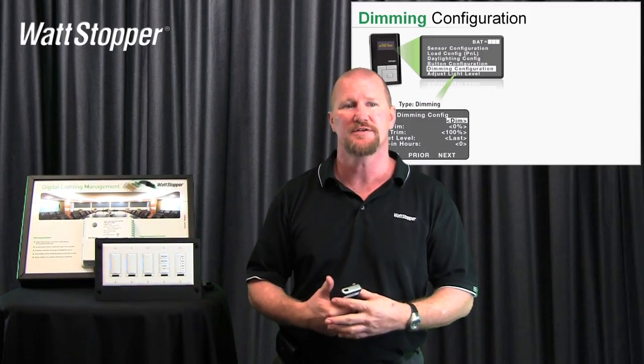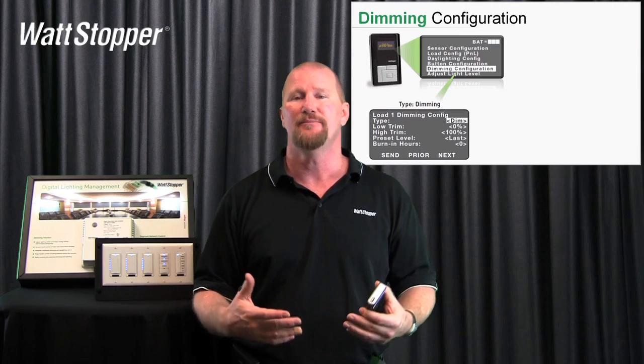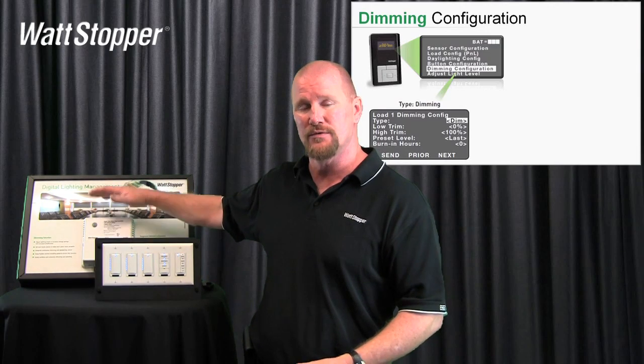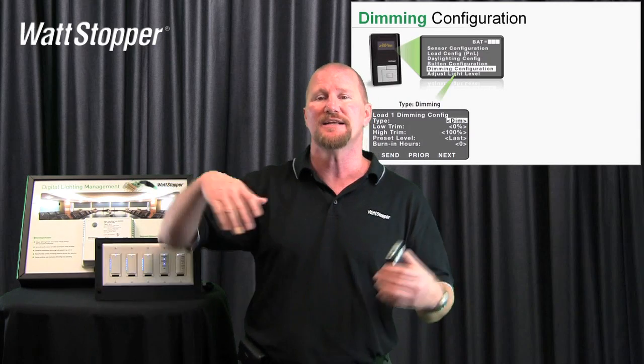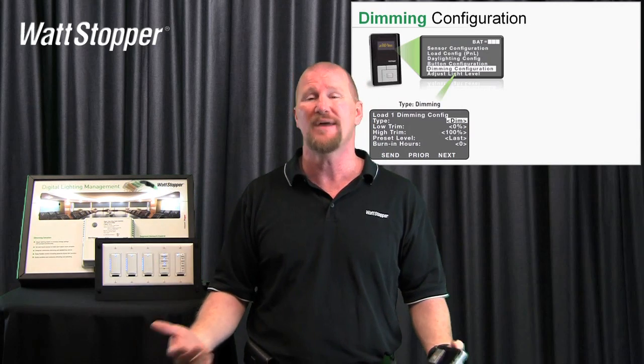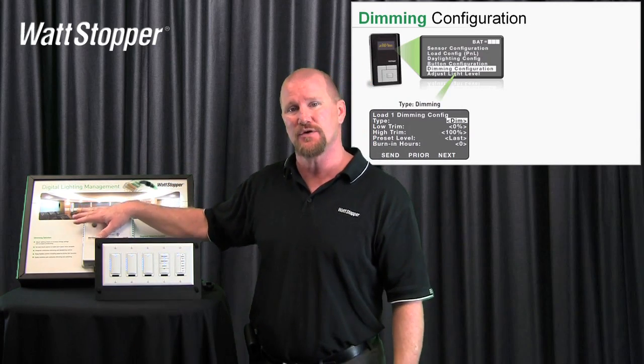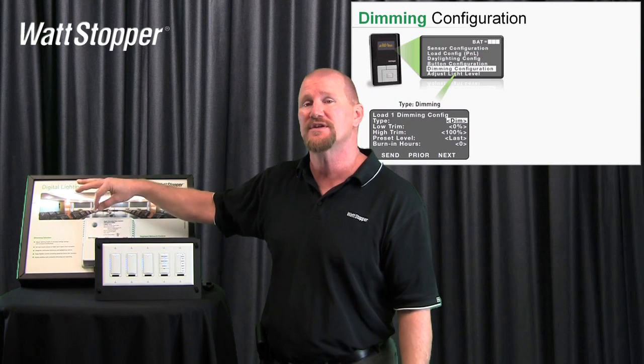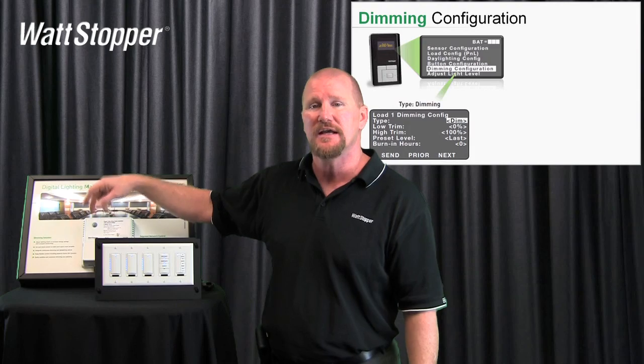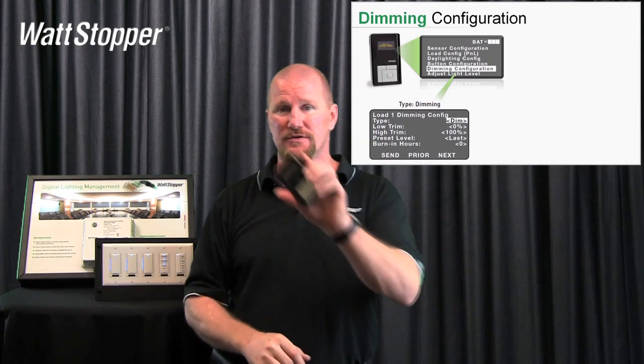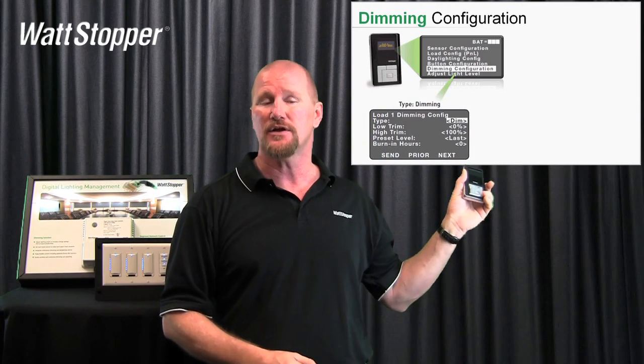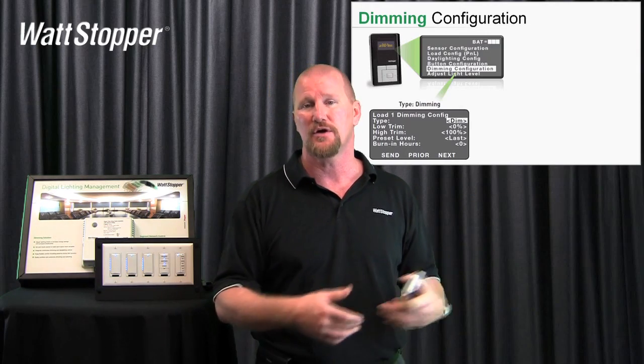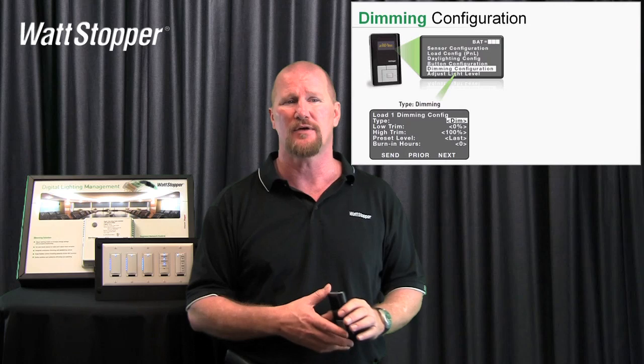If you look back to the PowerPoint, you'll see I can change the type — is it a dimmed load or a switched load? Since this room controller will do dimming or switching, we had to default it as something. So by default, this thinks it's controlling dimmed loads because we felt like most of the time it will be. If you have a switched load connected to one of these channels, it's really a good idea to use the LMCT100 and change the load type to switch. All the other changes will happen automatically — all you have to do is tell me it's a switched load and I'll make the changes for you in the background.